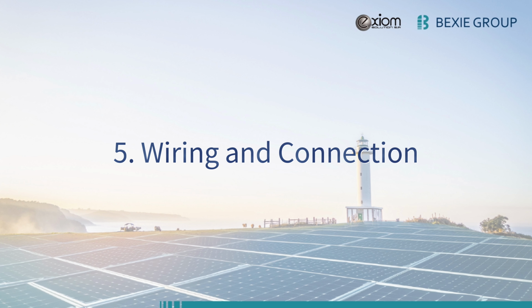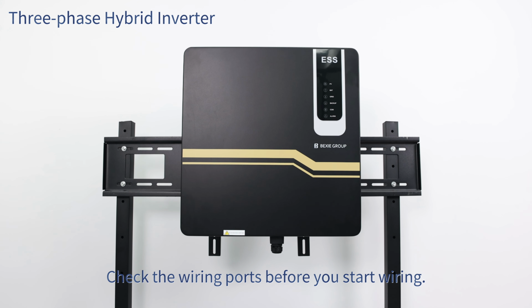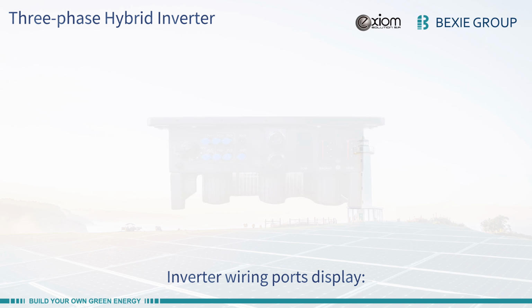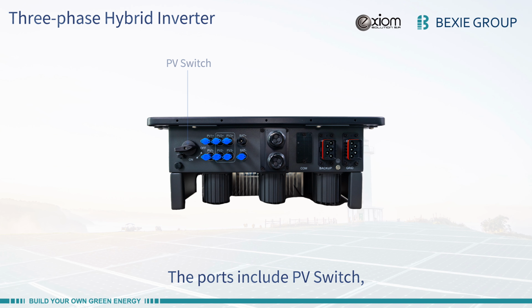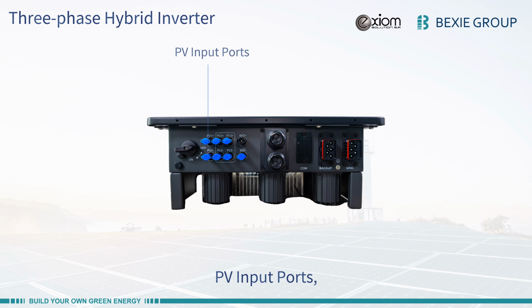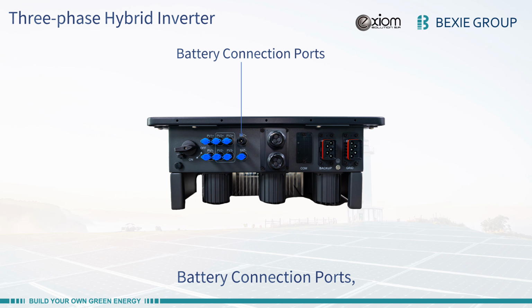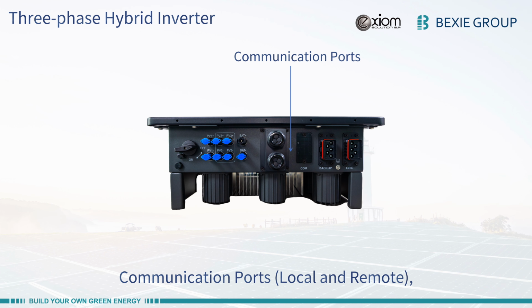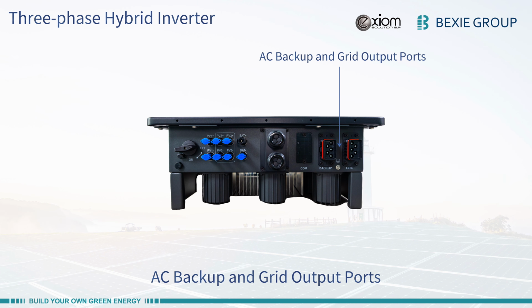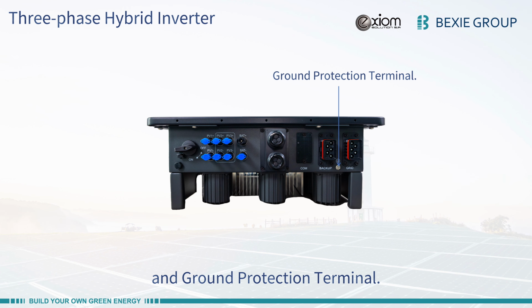5. Wiring and connection. Terminals display. Check the wiring ports before you start wiring. Inverter wiring ports display. The ports include PV switch, PV input ports, battery connection ports, communication ports, local and remote, AC backup and grid output ports, and ground protection terminal.